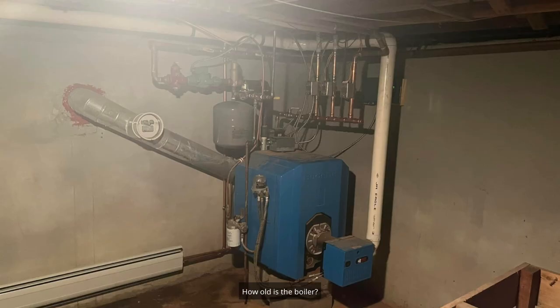Question 2: How old is the boiler? Cast iron boilers from quality brands — Buderus, Burnham, Weil-McLain — routinely last 40 to 60 years if they're maintained. Modular condensing boilers from the last 20 years are different; they have a 15 to 20 year design life. So 20 years old means very different things depending on the kind. Find the data plate, look up the model, and you'll know which curve you're on.